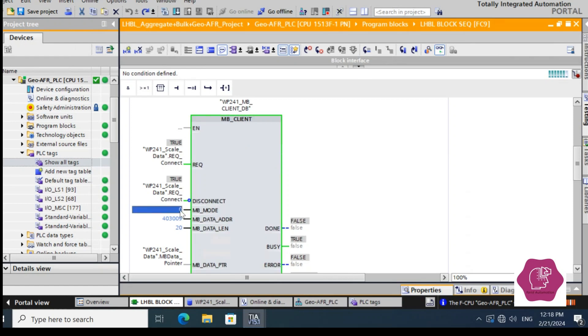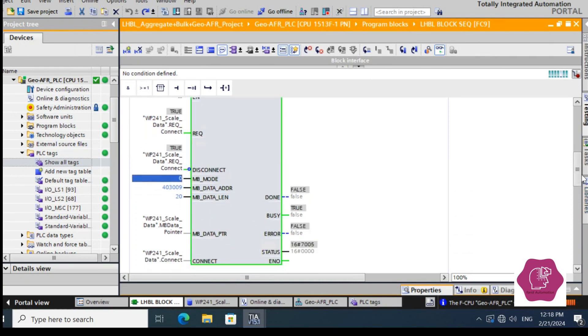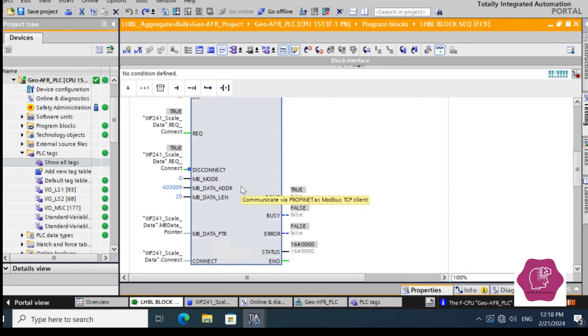MB_MODE must be set to 0 for reading data from the Modbus server. For our case, we need to read data from the Modbus server, so we have set it to 0. As shown in the PDF file, our data starts from address 3008; adding 1 gives 3009. It is an extended holding register, so the MB_DATA_ADDR is 403009.